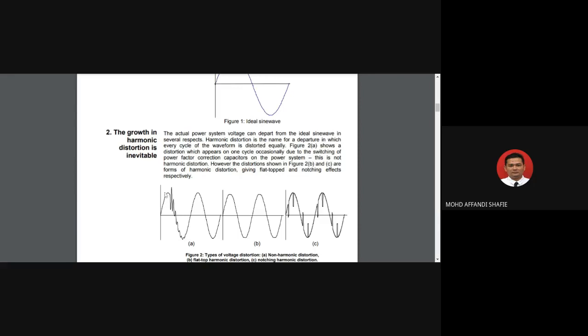Okay, so this is caused by the power factor correction capacitor on the system. This is not harmonic distortion. So this is more to do with switching. Switching means that this is a transient. If you refer back to chapter 3, we discussed the voltage swell. One of the causes is the switching of the capacitor in a power system. So you can refer back to chapter 3, right? So this is not a harmonic distortion from figure A.